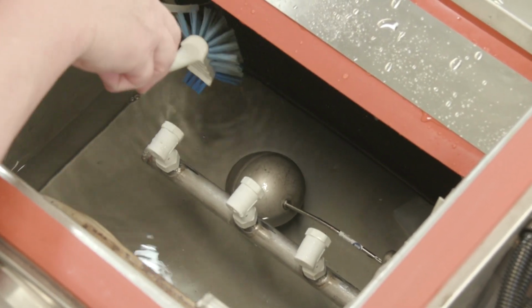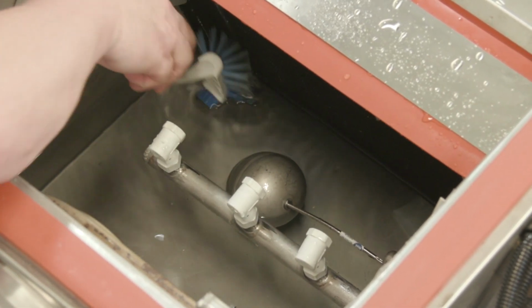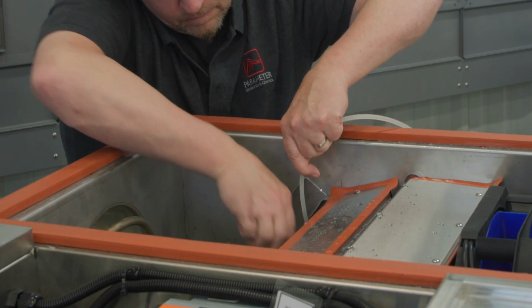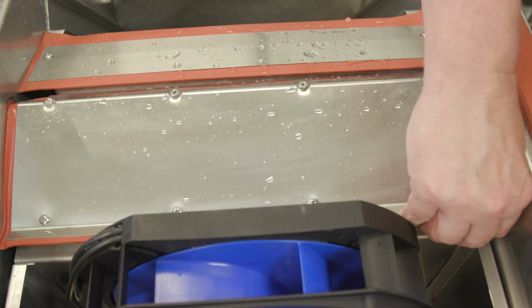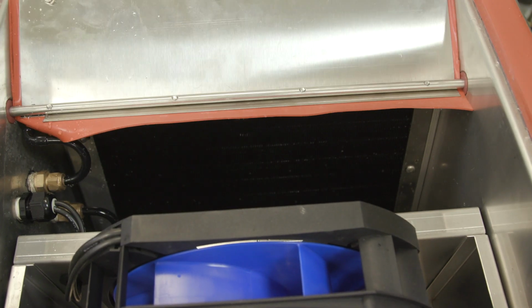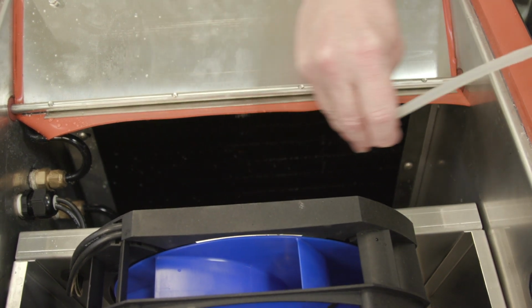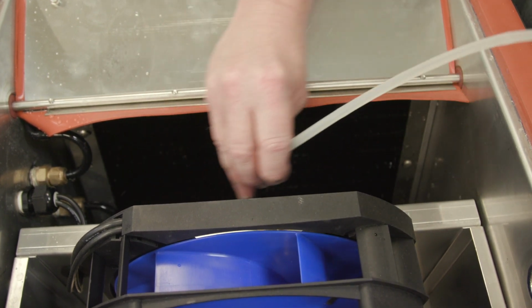Remember that the coil can be blocked between the fins and still look clean on the surface. Pressure washing is typically the only effective way to get the gunk from deep between the fins. Remove the damper and whatever else in order to access the hard-to-reach side of the coil. On vertical units in particular, be sure to remove the top cover on the coil and clean beneath.